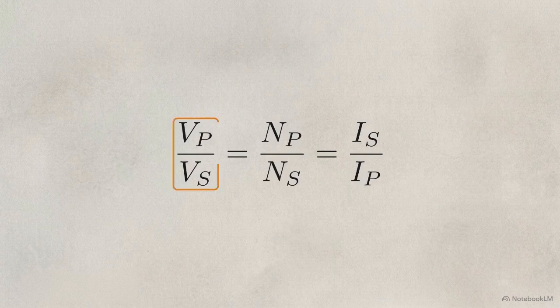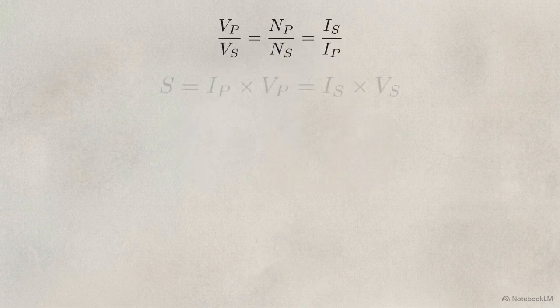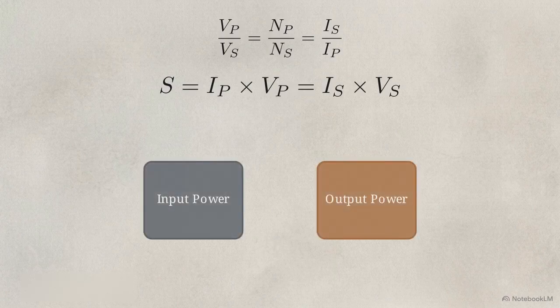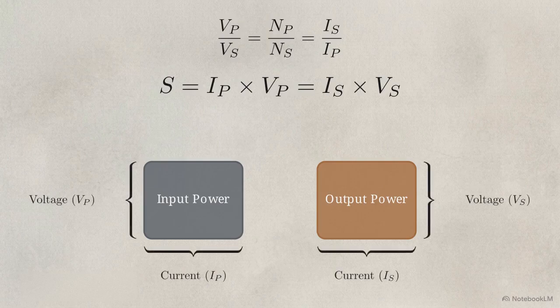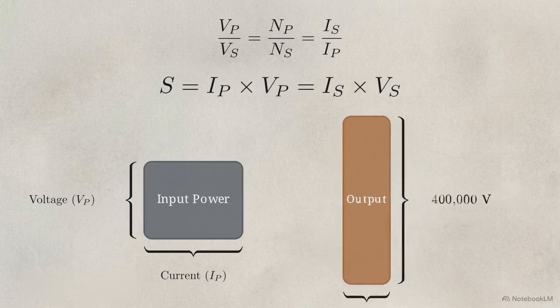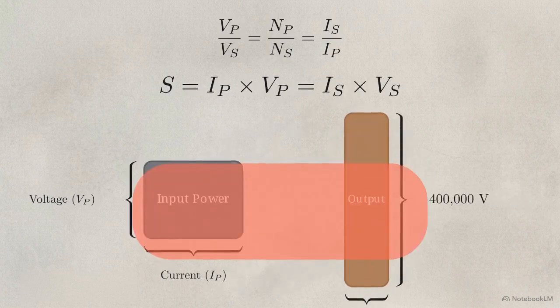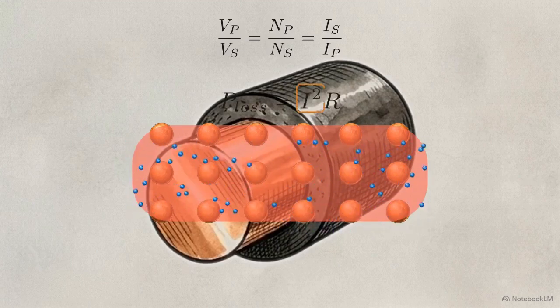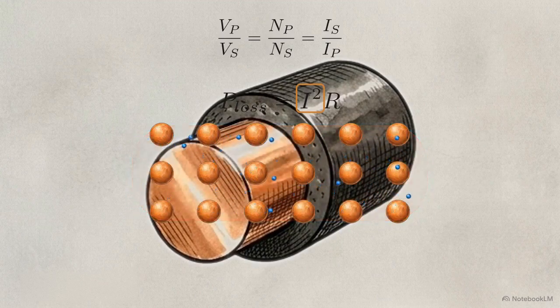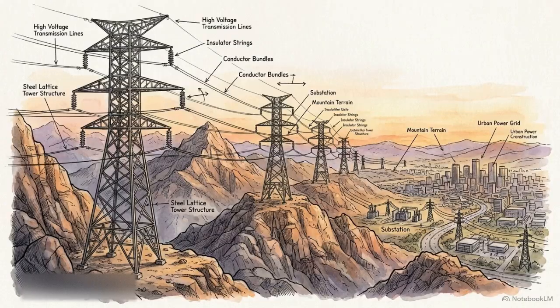It defines the fixed mathematical relationship between voltage, current, and the physical turns of wire within the device. According to the law of conservation of apparent power, total power must remain constant between the input and the output. Because power is the product of voltage and current, these two variables are inversely proportional. When a transformer steps the voltage up to 400,000 volts, it forces the current down proportionally. Because joule heating is tied to the square of that current, the thermal loss in the transmission lines drops to near zero. This mathematical decoupling of voltage and current is the mechanism that enables modern long-distance electrical infrastructure.